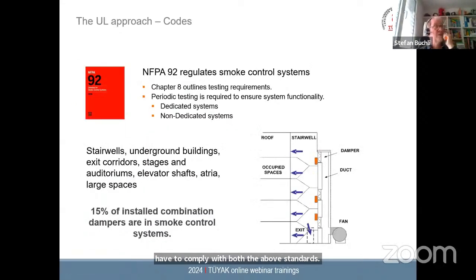And there is another one, the so-called NFPA 92, which regulates dedicated smoke control systems. So there is a separate standard for that. But today, when we look at the installation of the combination fire smoke dampers, only roughly 15% of these dampers are installed in the smoke control systems. So very often it's done via the ventilation system, and the part or the numbers of the really dedicated smoke control system is still quite small.